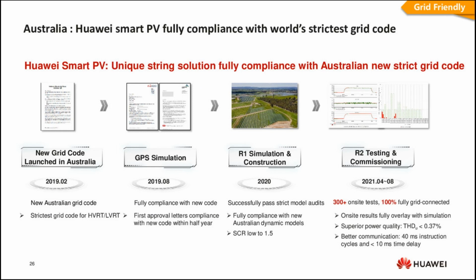A case from Australia shows a very stringent and robust grid code validation process, both before and after construction. I am happy to share that we are one of the smart PV string inverter solutions with full compliance and operation notification under Australia's strict grid code conditions, with robust tests and validations covering RMS and EMT level models, as well as performance at the power plant site level.